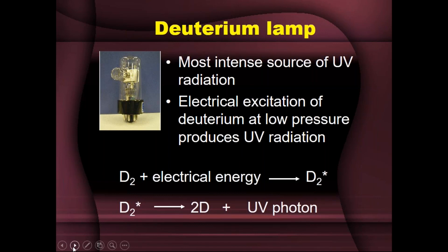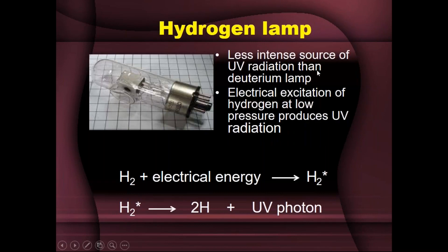Then there is the hydrogen lamp, similar to the deuterium lamp, except the bulb is filled with hydrogen at low pressure. Electrical excitation of hydrogen at low pressure produces UV radiation; the excited H₂* molecule dissociates to give two hydrogen atoms releasing one UV photon. It also emits radiation from 160 to 375 nanometers, just like the deuterium lamp, but it is a less intense source of UV radiation than the deuterium lamp.